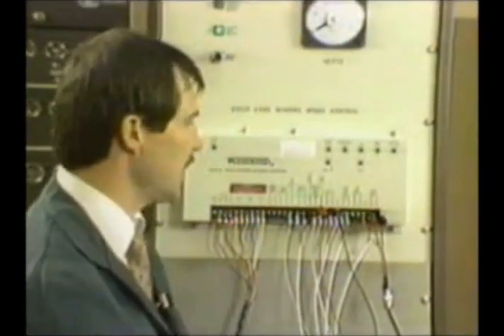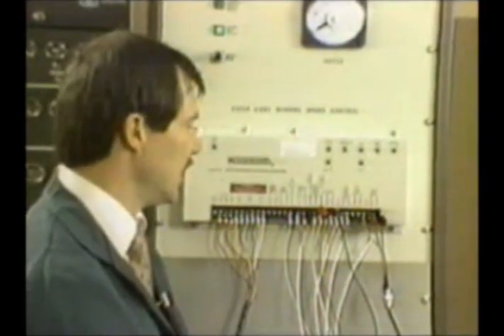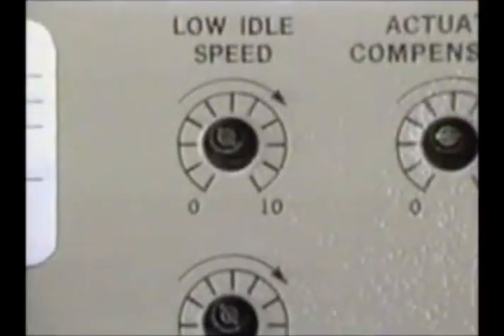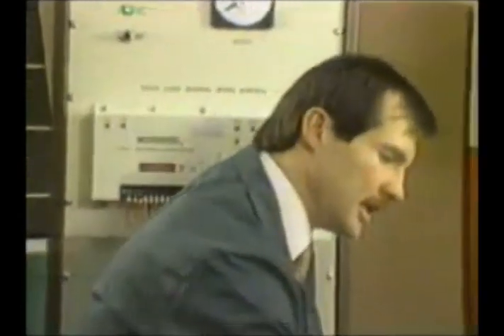Well, since I can control at 4680, I might as well set up an idle speed. I want to run at an idle speed on this. I have my idle pot fully clockwise right now. I want to figure out my idle speed, which I'm going to set for 1200 RPM here, so I can quickly take 156 times 1200 and divide that by 60, and that tells me I want to set my idle speed for around 3,120 hertz.